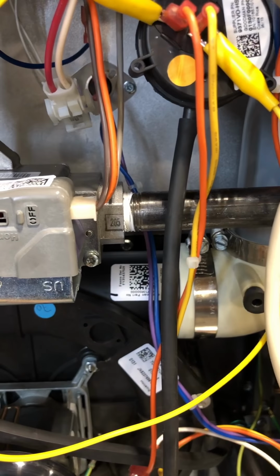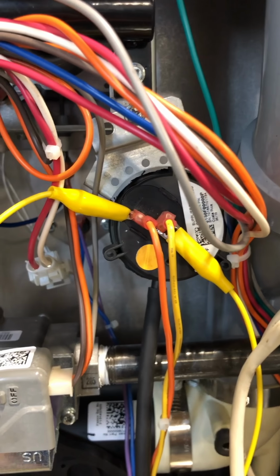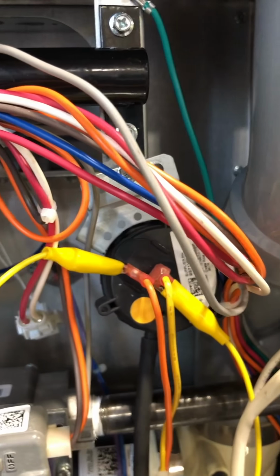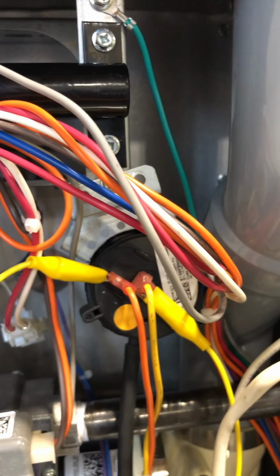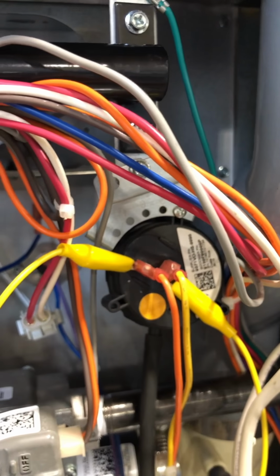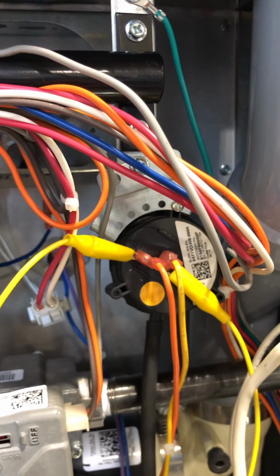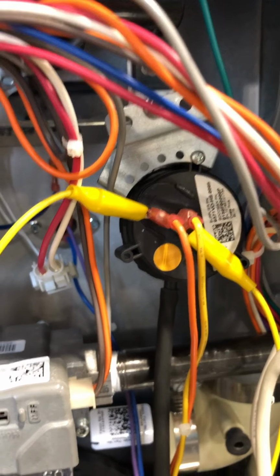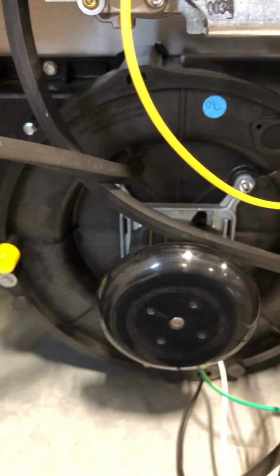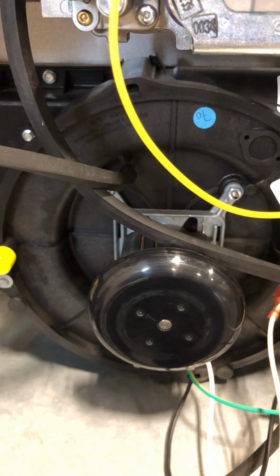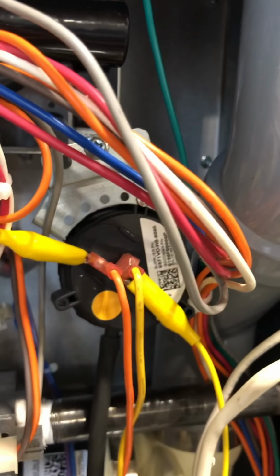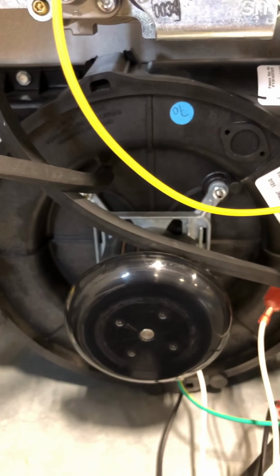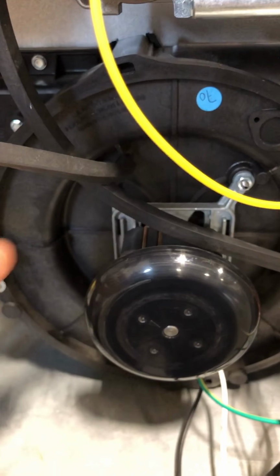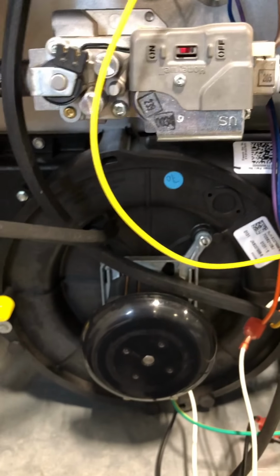Then it will bring on the inducer. I've had guys tell me, no, it's just a call for heat, then the inducer comes on, and then that switch closes. Well, what if that switch stuck closed the last time that this furnace fired up? And it's still passing that 24 volts as if this inducer was running. Now the likelihood of this sticking closed and the inducer motor flat out not working on the next startup is very remote, but the possibility is there, especially on older equipment.